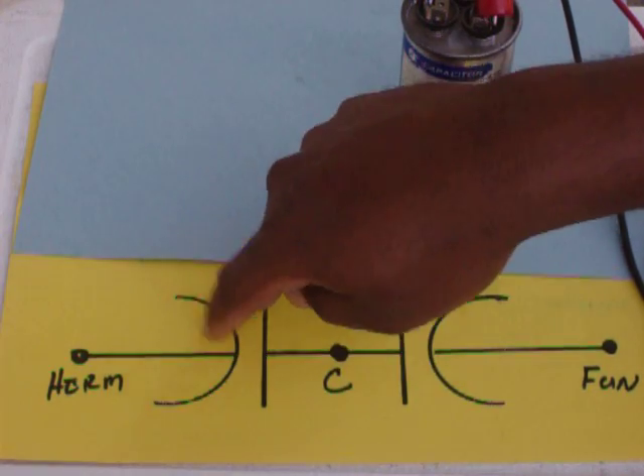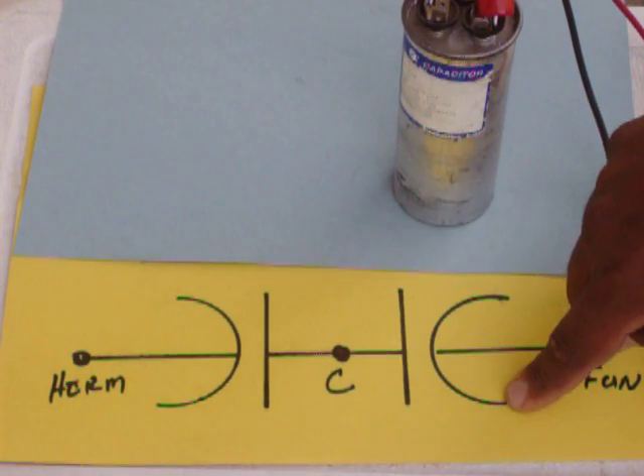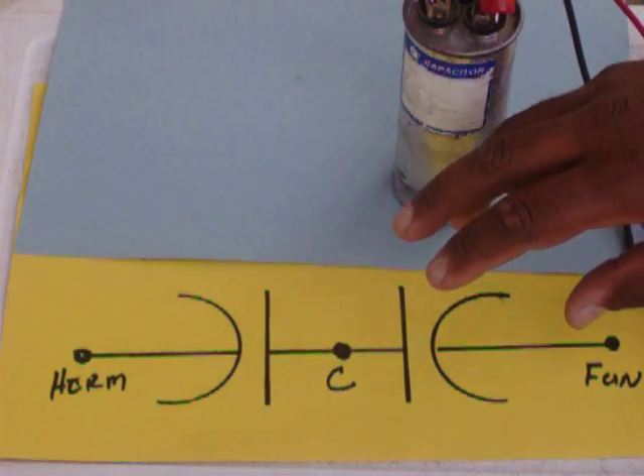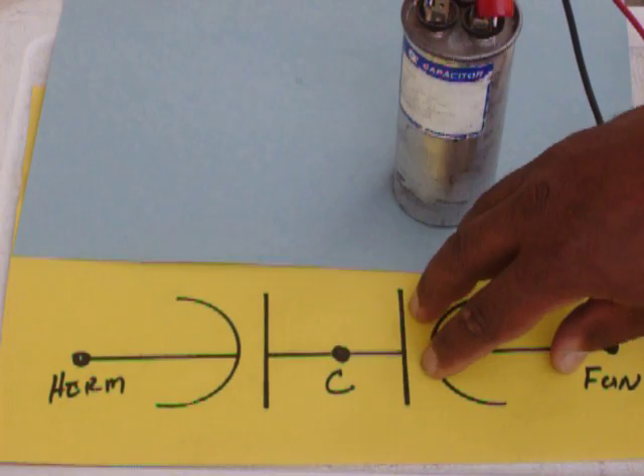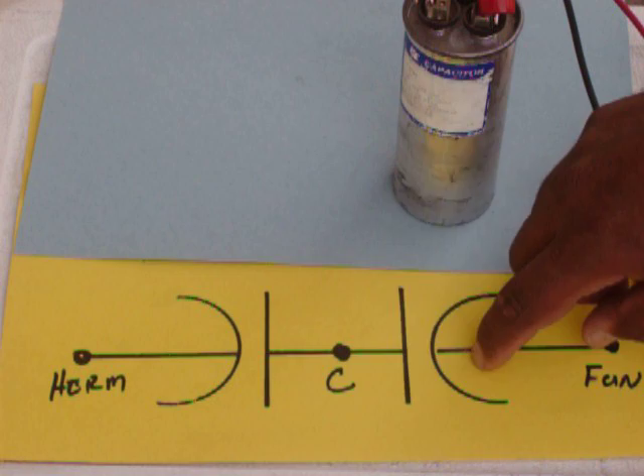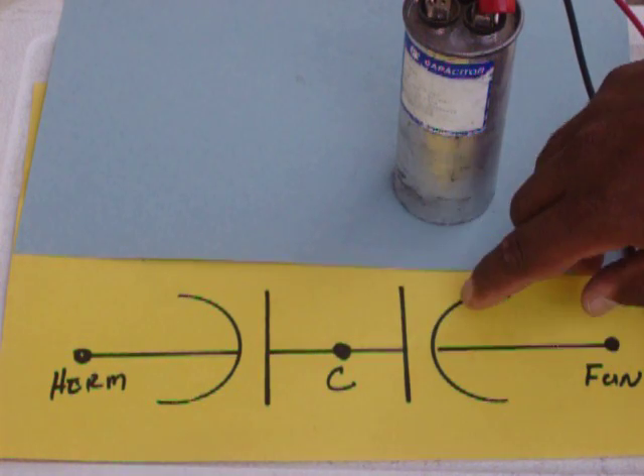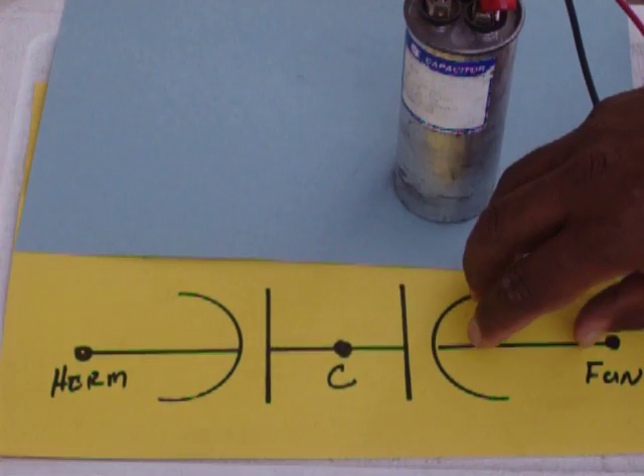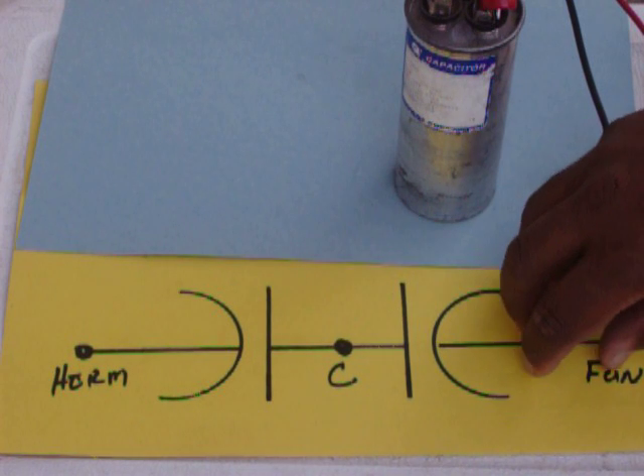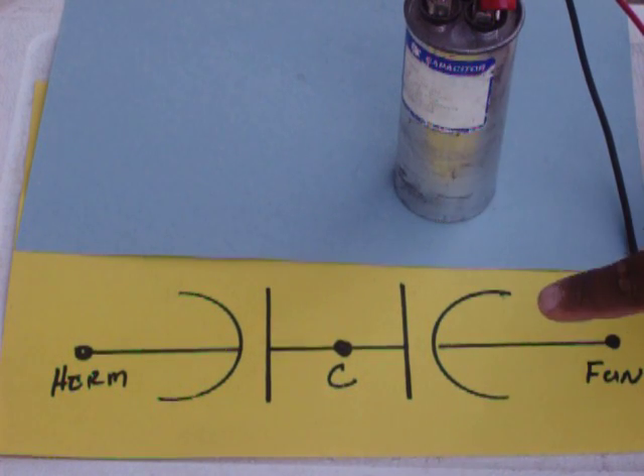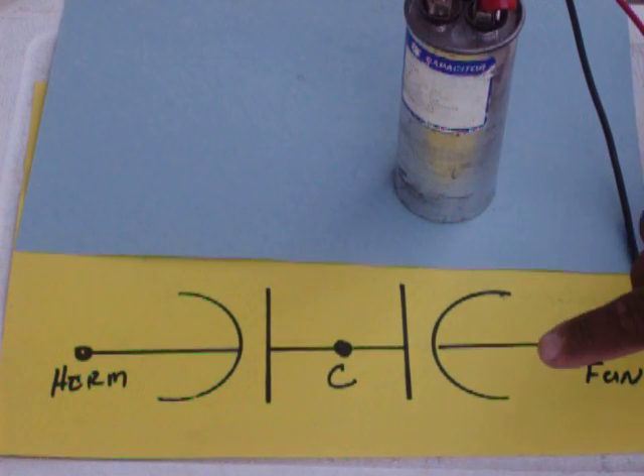It is possible to lose your fan side and the hermetic is still good. Lose your hermetic side and your fan is still good. So you can still have this, lose this and just add another capacitor. But it's always easy to just change the whole capacitor. Whenever you change the capacitor, make it easier on yourself and go back with the exact same capacitor that was in originally.